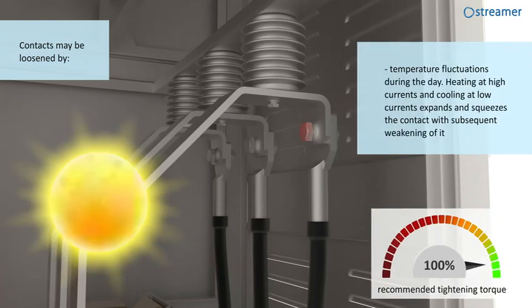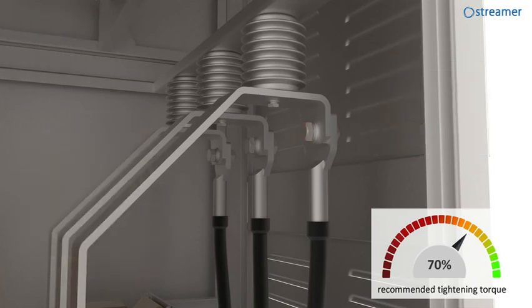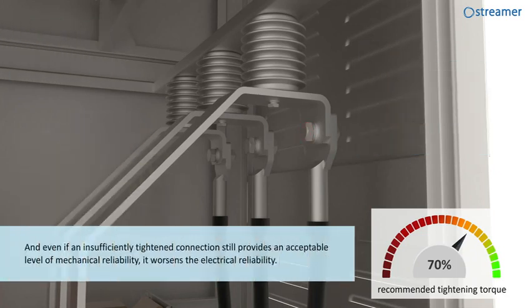temperature fluctuations during the day, heating at high currents and cooling at low currents expands and squeezes the contact with subsequent weakening of it. And even if an insufficiently tightened connection still provides an acceptable level of mechanical reliability, it worsens the electrical reliability.